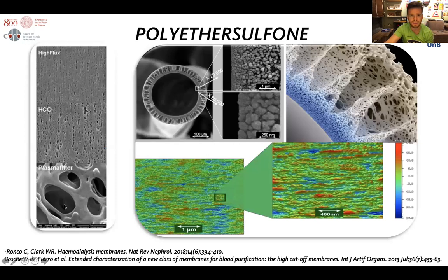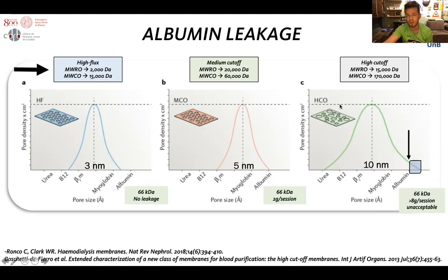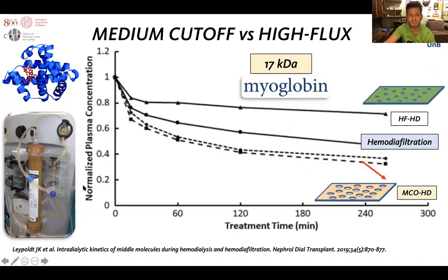We also have new membranes and new filters. On the left we show the scan microscopy of a high-flux filter, a high-cutoff filter, and a plasma filter for example. The newest membranes are the medium-cutoff membranes, which are the most modern membranes so far. They have a pore size larger than the high-flux membrane, albeit smaller than a high-cutoff membrane. This membrane is more uniform in most of its pores — on the y-axis we have pore density, which is more concentrated and more uniform than the high-cutoff membrane. However, due to this uniformity, many pores allow passage of albumin, and albumin leakage is an issue when high-cutoff membranes are applied.